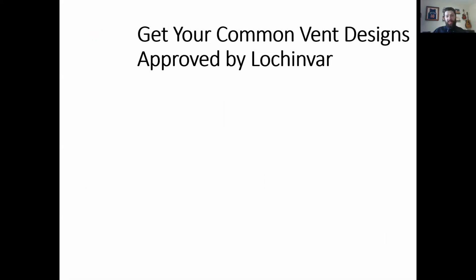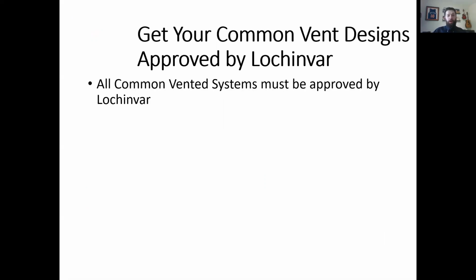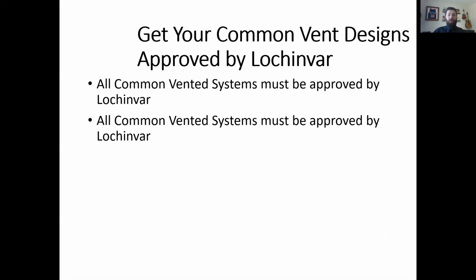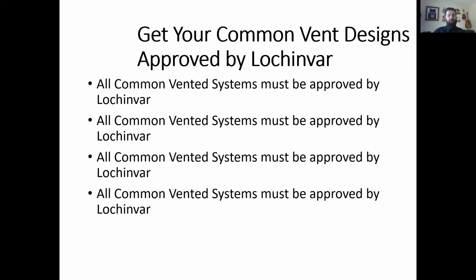When you're using a Crest, guys, you got to get your common vent designs approved by Lochinvar. All common vented systems must be approved by Lochinvar. And I'm going to say it two more times. Really important. If you've got a common vented system, we're going to take care of it for you and cover it, but you just got to let us know. We are common venting. We're going to get it out to the professional and local team that Lochinvar employs to approve this and make sure that you're going to have a functioning model.